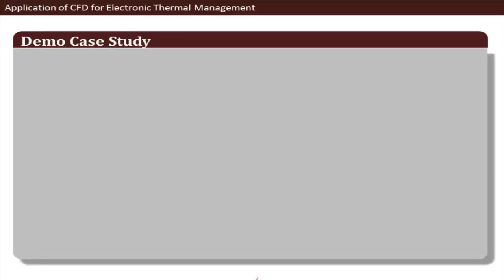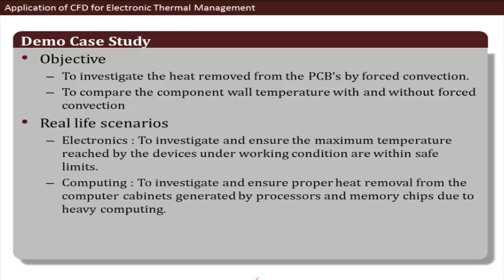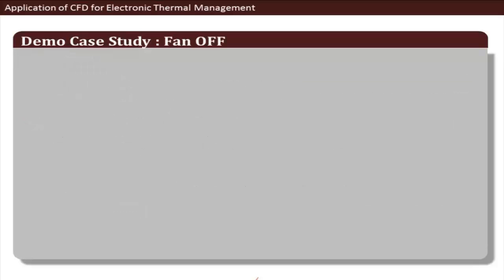We'll now see a demo case of a cabinet-level simulation done using the general-purpose code ANSYS Fluent. The objective was to investigate heat removal from PCBs by forced convection and to compare component wall temperatures with and without forced convection. Real-life applications include ensuring maximum device temperatures under working conditions stay within safe limits and ensuring proper heat removal from computer cabinets. The first case is the worst-case scenario with the fan off.